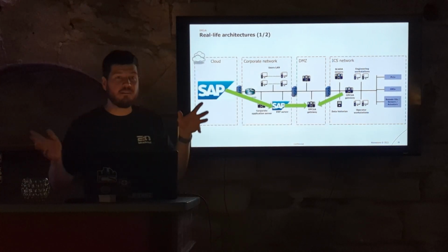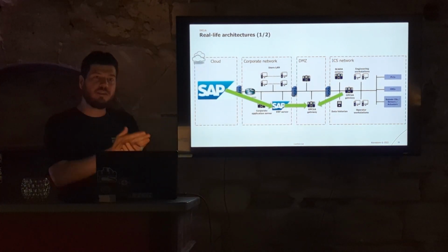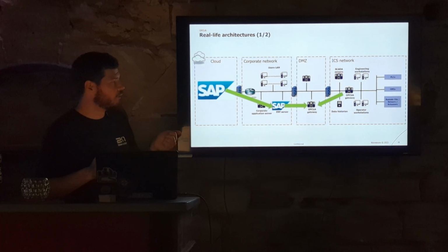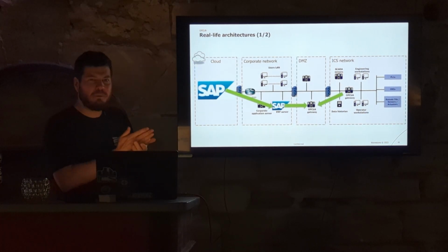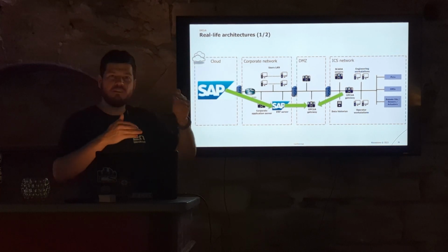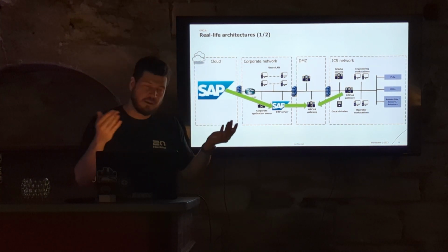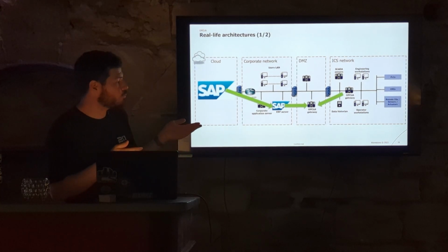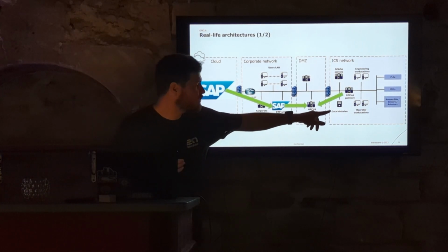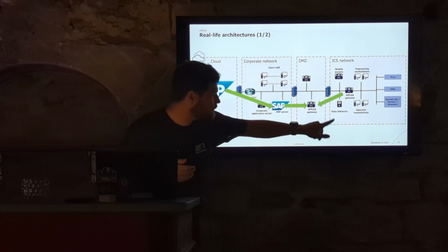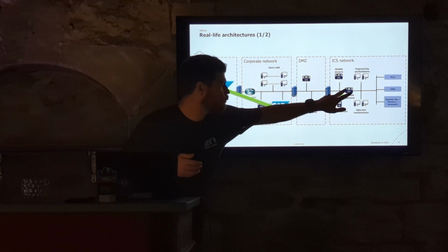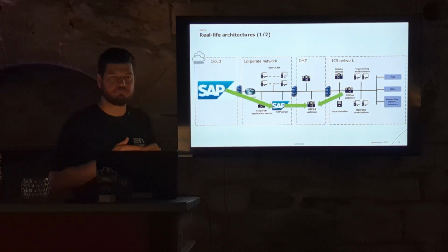It gets all the data from everything in the process and stores that in a time-based database. So the idea is that at any point in time, you can go back and say, okay, the value of these sensors was that, and you can do some analysis on how to improve your process. And so yes, you could probably do the same with the data historian, but most of the time those will not be two different machines. It will be the same.